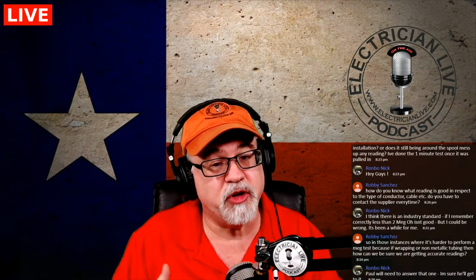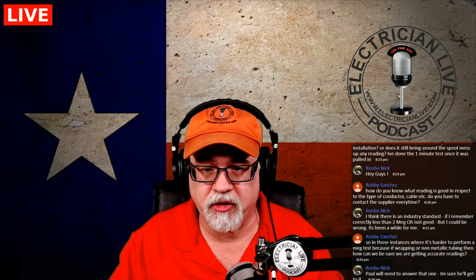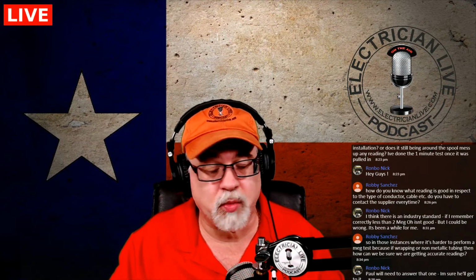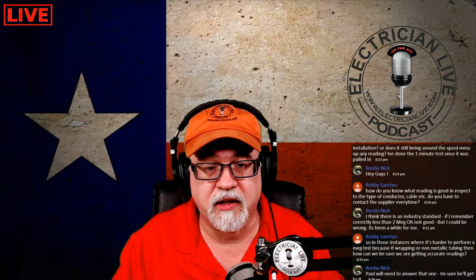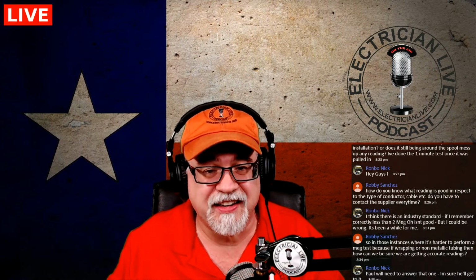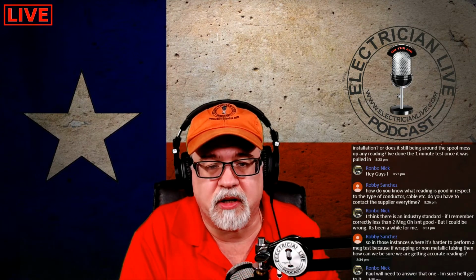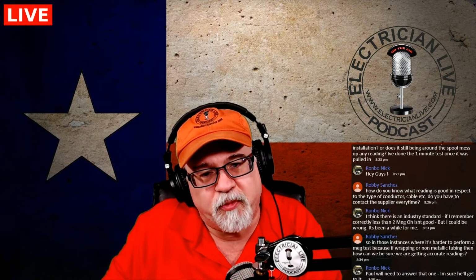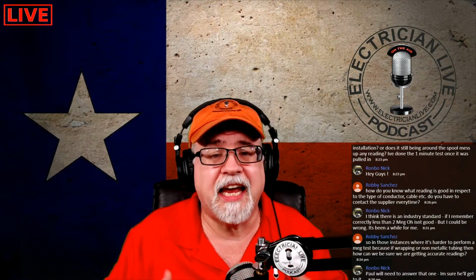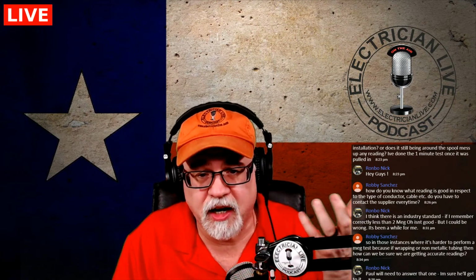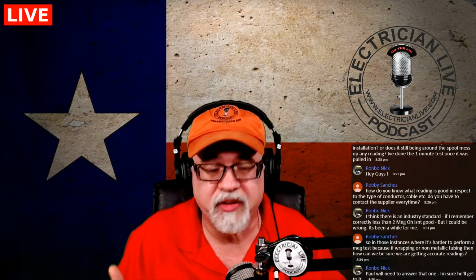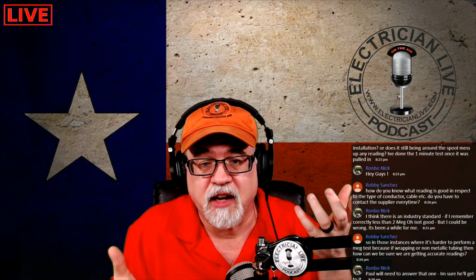So I'm not saying you have to every time. You're probably not going to run into this every time. But if you do get it, remember, there are many things that could cause this to happen. Humidity, temperature, moisture retention, water between the interstices of the individual conductive material, mutual capacitance because you were charging 2 conductors and then the next one didn't get discharged before you tested it. All these types of things can contribute to it. But just because one is a gigaohm and the other one's only 50 megaohms does not mean that this conductor at 50 megaohms is bad. It's just not 1 gigaohm, okay?